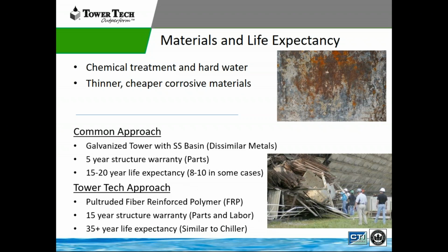Okay, so a traditional tower system uses a galvanized tower and a stainless steel basin. Those are two dissimilar metals, which could cause galvanic corrosion. It has a 5-year structure warranty, which is parts only, and per ASHRAE a 15 to 20 year life expectancy, 8 to 10 in some cases, depending on the water quality. Tower Tech's approach is a pultruded fiber reinforced polymer cooling tower with a 15-year structure parts and labor warranty on the tower structure itself, and a 35-year life expectancy.